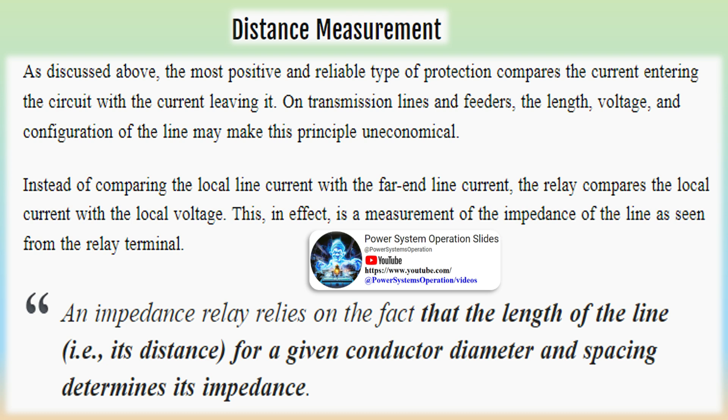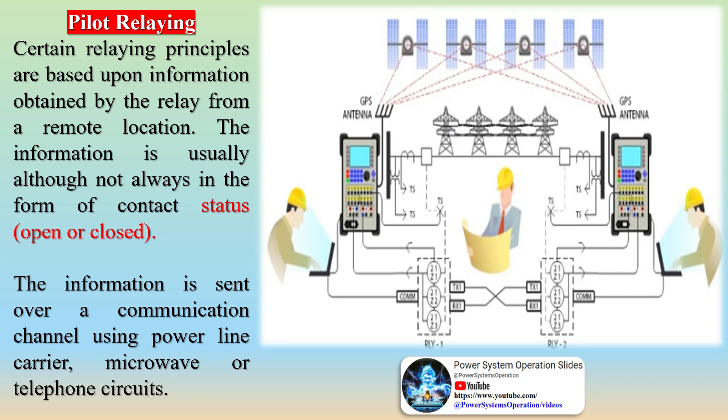Instead of comparing the local line current with the far end line current, the relay compares the local current with the local voltage. This, in effect, is a measurement of the impedance of the line as seen from the relay terminal. An impedance relay relies on the fact that the length of the line, i.e. its distance, for a given conductor diameter and spacing determines its impedance.